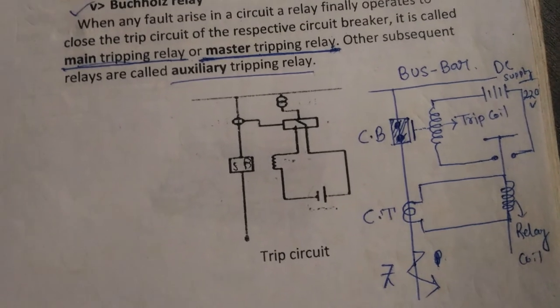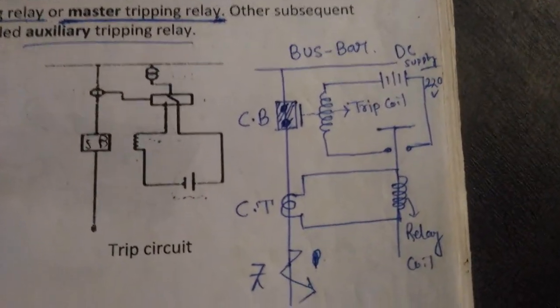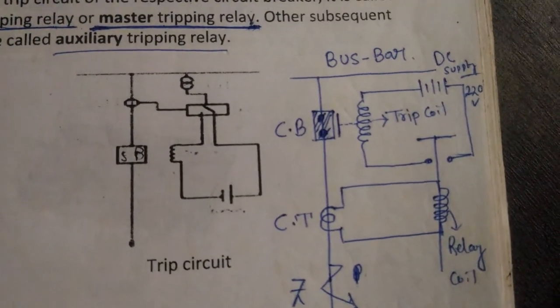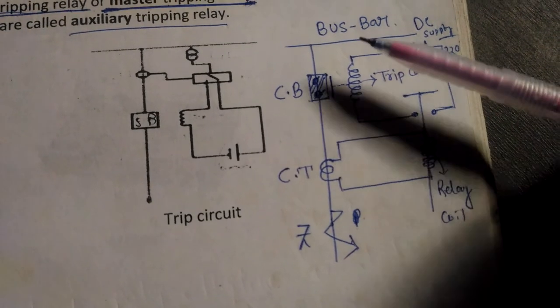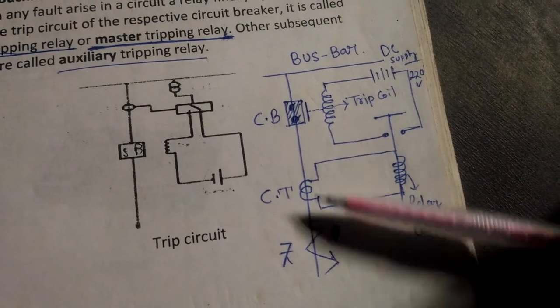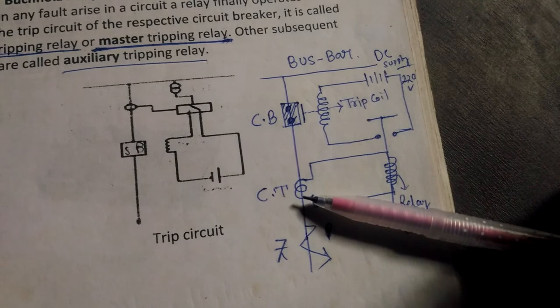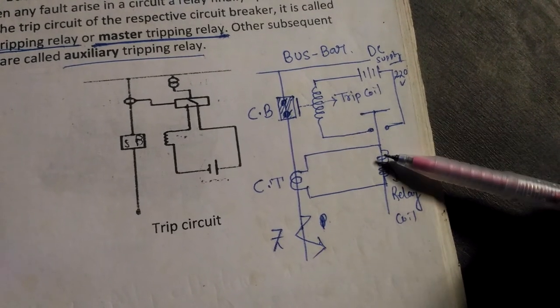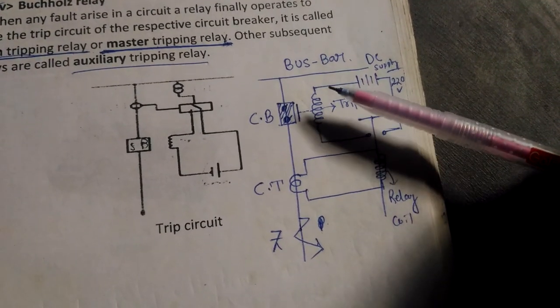Here is a pictorial representation of the total protection circuit and how it operates. If some fault occurs at a location, the fault current flows through this path to the CT coil. The enormous current flows through this path, and if the primary side current increases, the secondary CT current will also increase. When the CT current increases, the relay is energized, the NC contact provides DC power to the trip coil, the trip coil operates, the circuit breaker opens, and the faulty section is isolated from the healthy bus bar section.